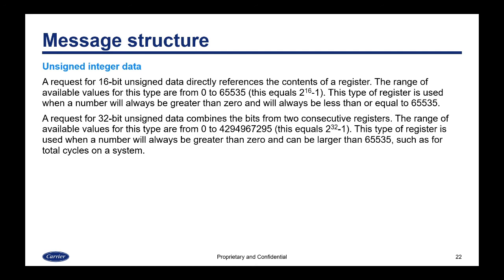A request for 32-bit unsigned data combines the bits from two consecutive registers. The range of available values is from 0 to 4,294,967,295 — about 4.3 billion — which equals 2 to the 32nd power minus 1. This type of register is used when a number will always be greater than 0 and can be larger than 65,535, and is typical for something such as total cycles on a system. It works by taking the contents of the two registers and combining all of the bits together to create one larger number.